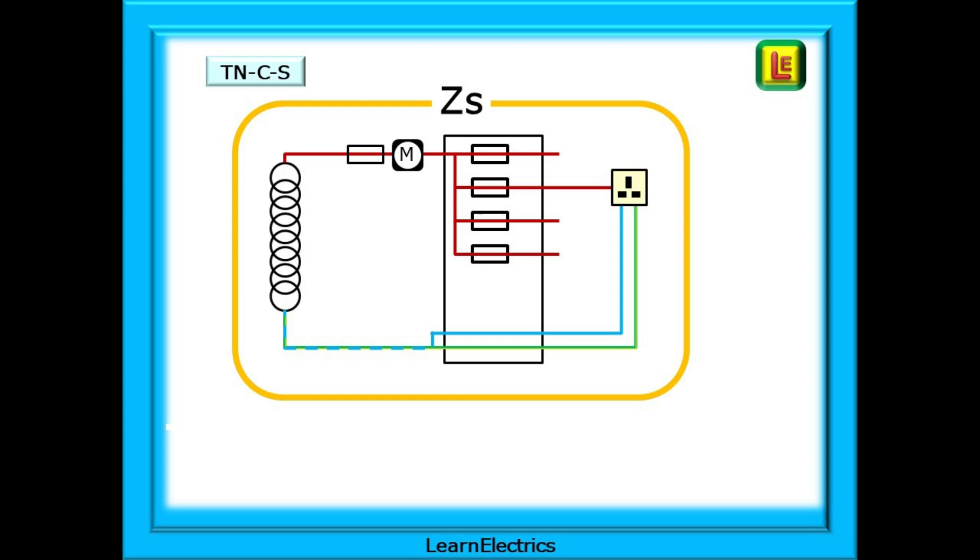If we look at this ZS drawing of a TNCS system, it is like the TNS drawing from earlier, but look again at the bottom of the supply transformer. The connection from the transformer to the consumer unit is just one conductor. In the external part of the installation, Earth and Neutral are combined together. Only at the consumer unit are they separated into two individual cables. Never to meet again.